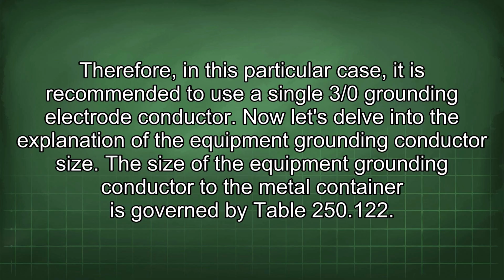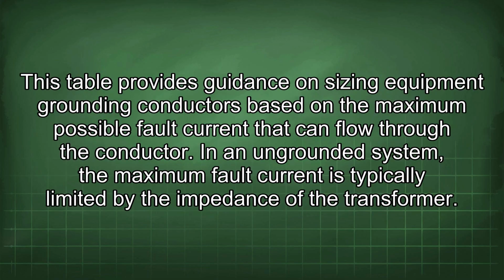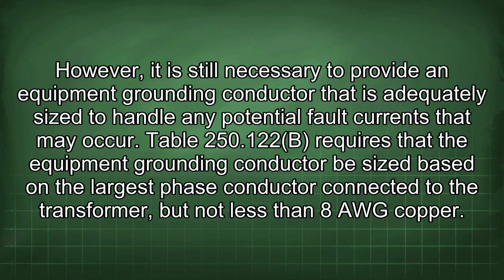Now let's delve into the explanation of the equipment grounding conductor size. The size of the equipment grounding conductor to the metal container is governed by Table 250.122. This table provides guidance on sizing equipment grounding conductors based on the maximum possible fault current that can flow through the conductor. In an ungrounded system, the maximum fault current is typically limited by the impedance of the transformer.